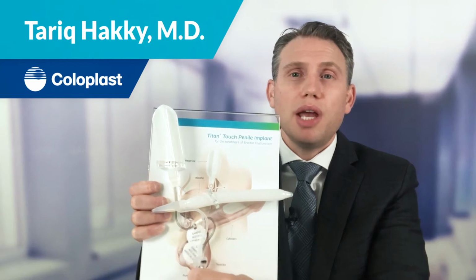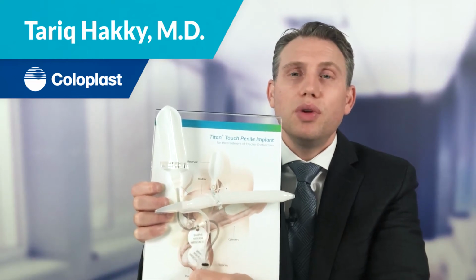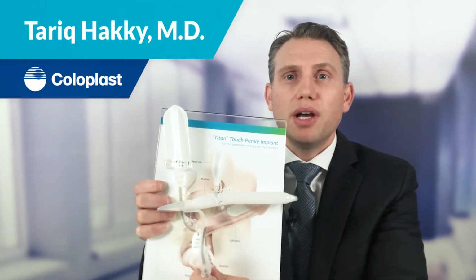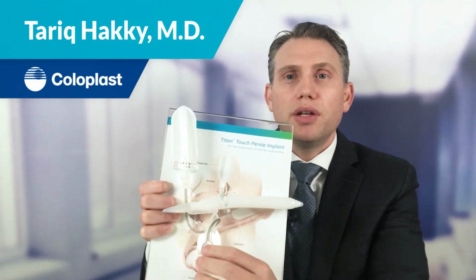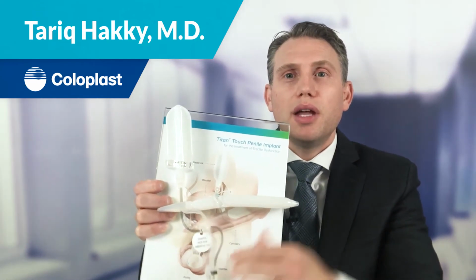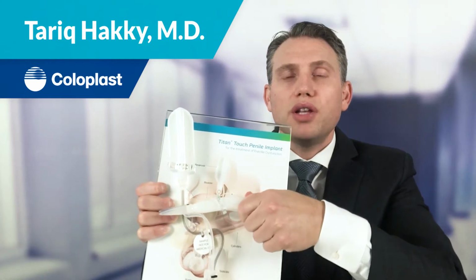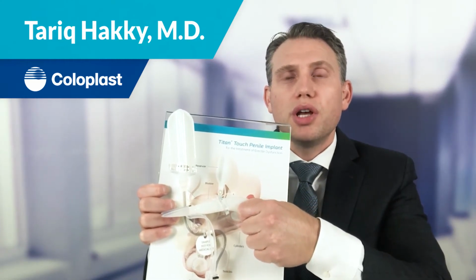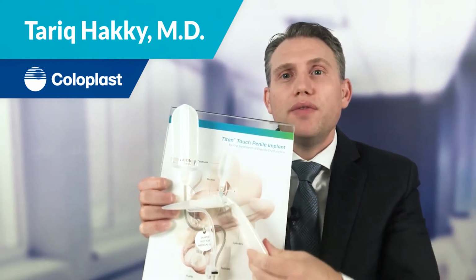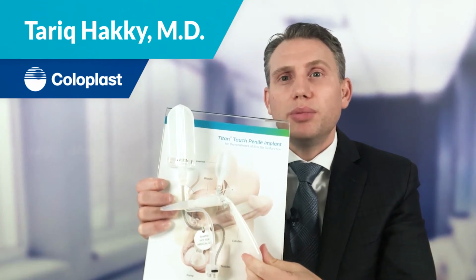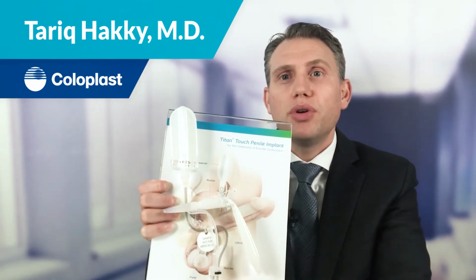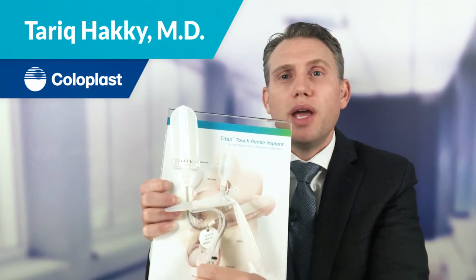The penile implant will stay erect until you hit the deflate button, which is found just above the pump itself. Here's the deflate button, and you can see once I've pressed it, I can then squeeze the shaft and transfer the fluids from the cylinders back to the reservoir. After you have successfully deflated the penile implant and you're happy with the fluid in this chamber, you can lock the device by hitting the pump button once.